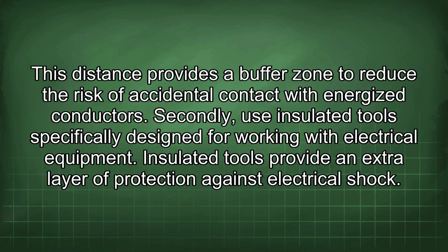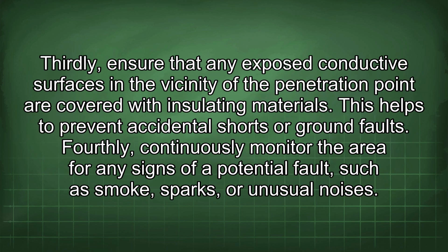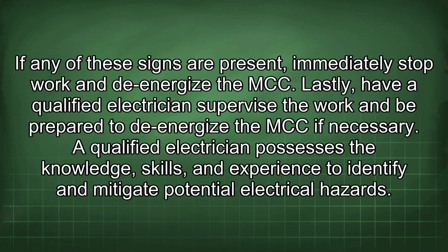Secondly, use insulated tools specifically designed for working with electrical equipment. Insulated tools provide an extra layer of protection against electrical shock. Thirdly, ensure that any exposed conductive surfaces in the vicinity of the penetration point are covered with insulating materials. This helps to prevent accidental shorts or ground faults. Fourthly, continuously monitor the area for any signs of a potential fault, such as smoke, sparks, or unusual noises. If any of these signs are present, immediately stop work and de-energize the MCC.